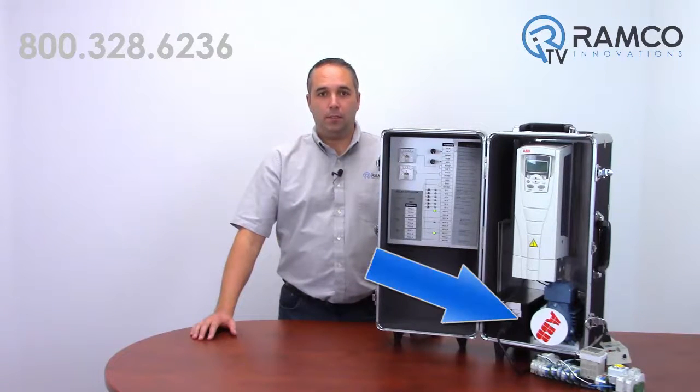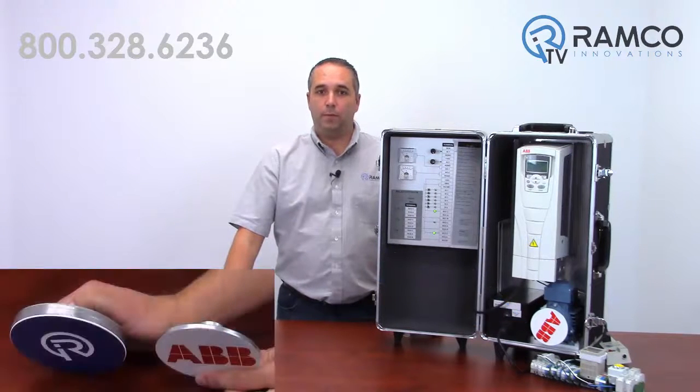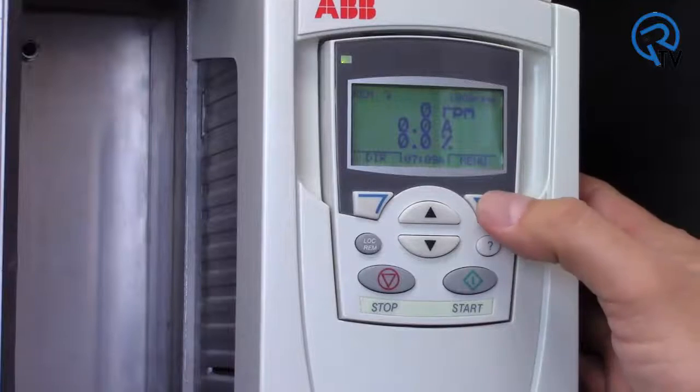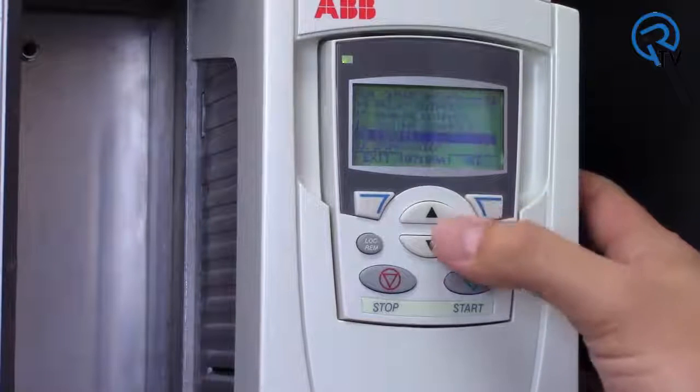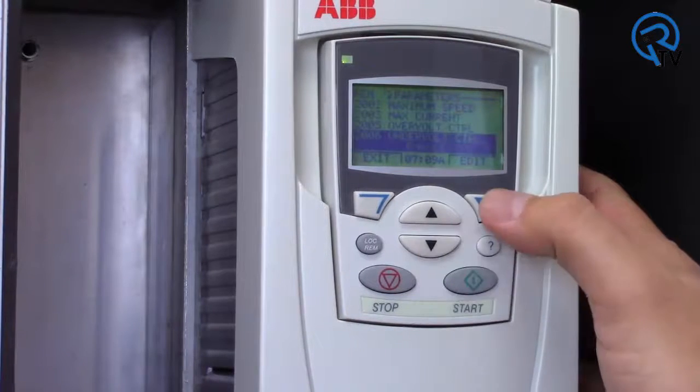If you look at my demo case, this little aluminum wheel does not have very much inertia when rotating, so it's hard to demonstrate this capability. So I've added this half inch thick solid steel wheel to simulate a high inertia load. The power loss ride-through capability is enabled by default on all ABB drives, so I need to disable it to first show you the functionality.